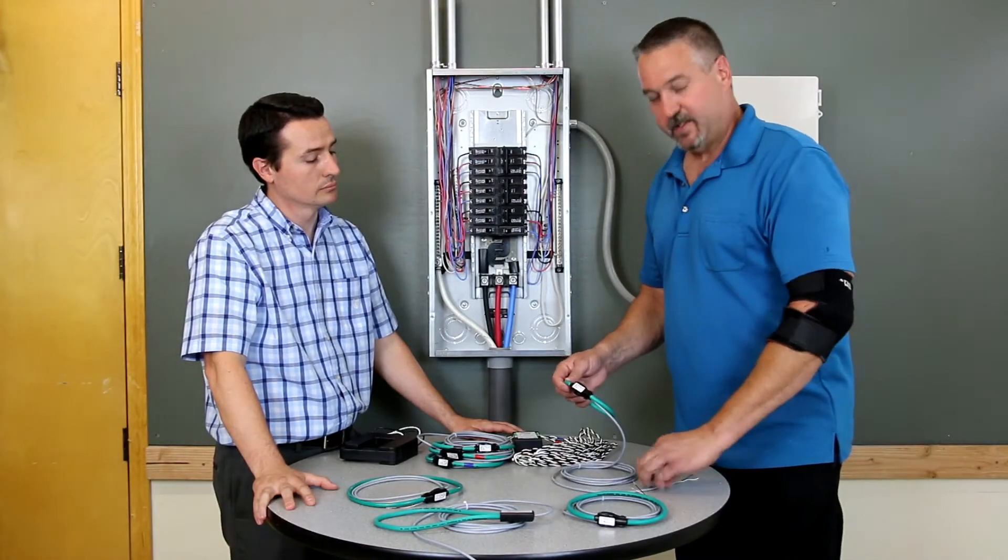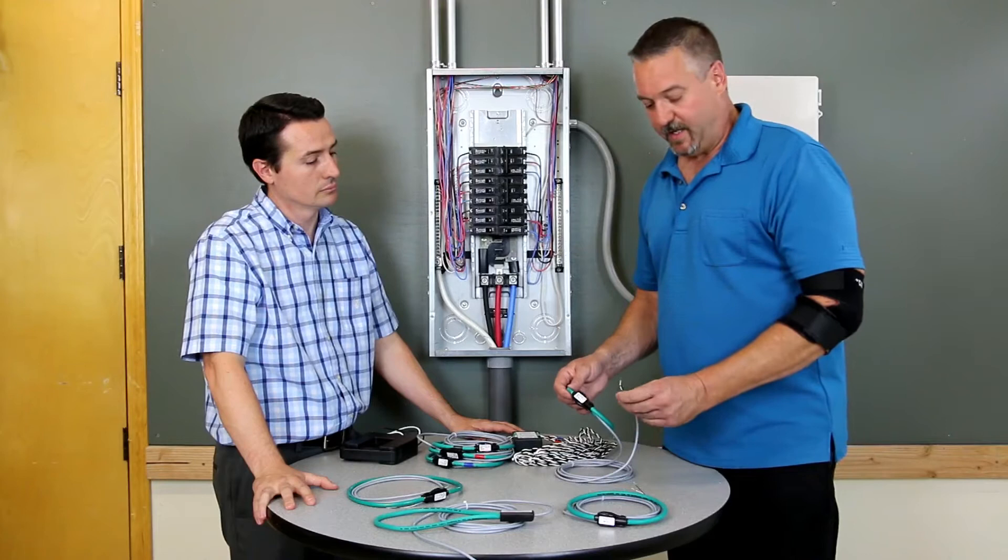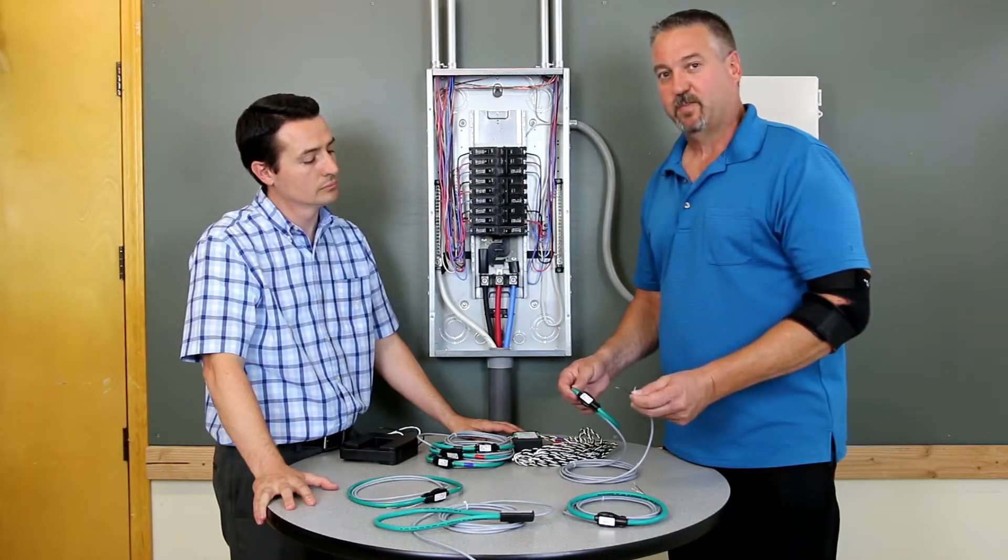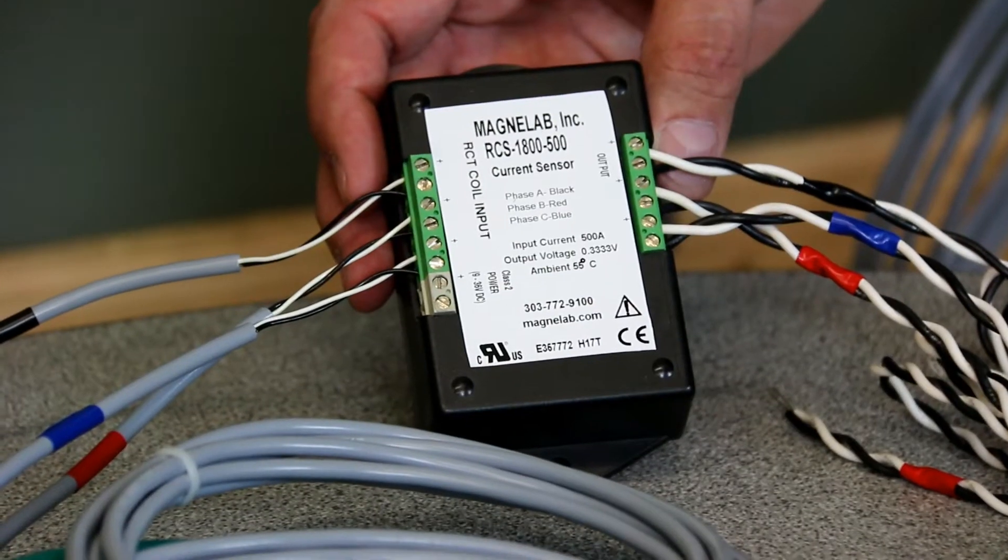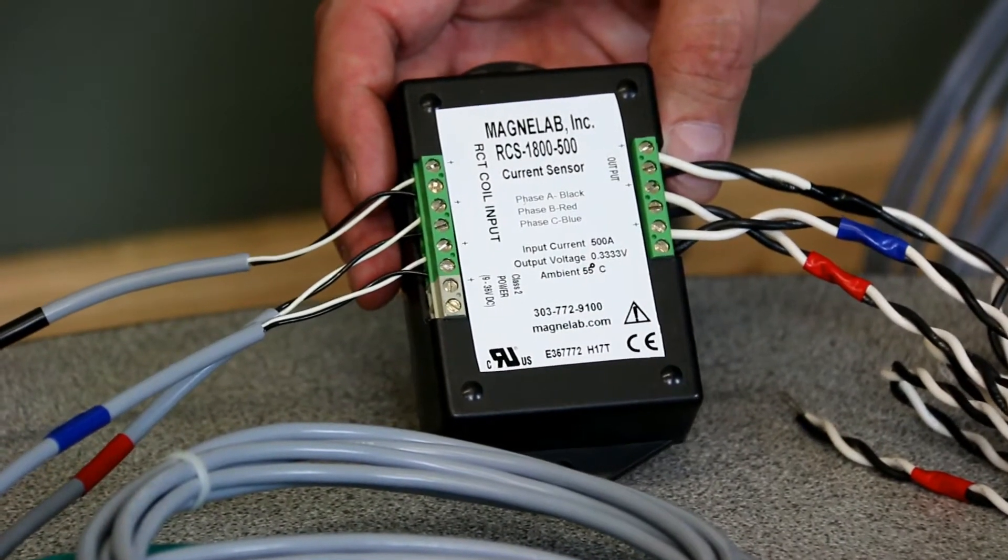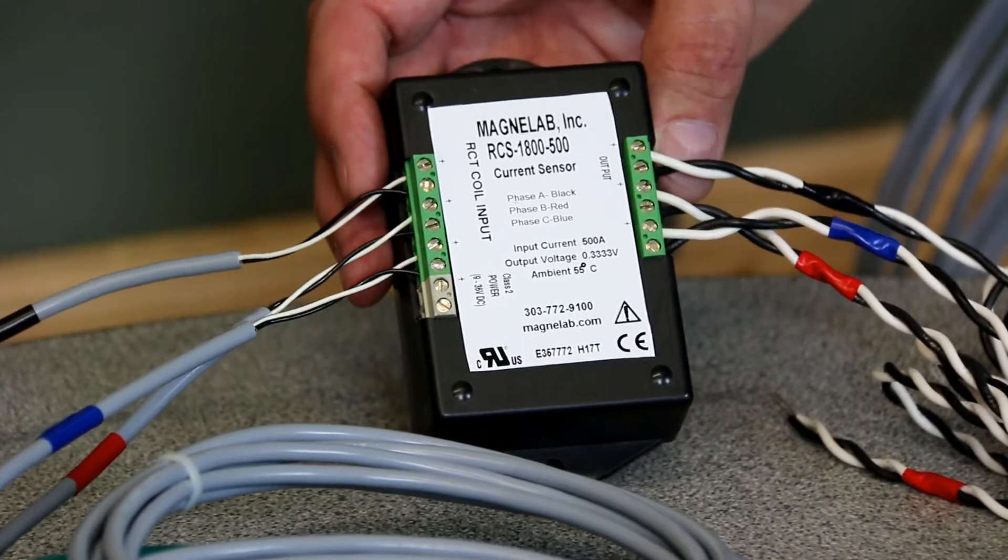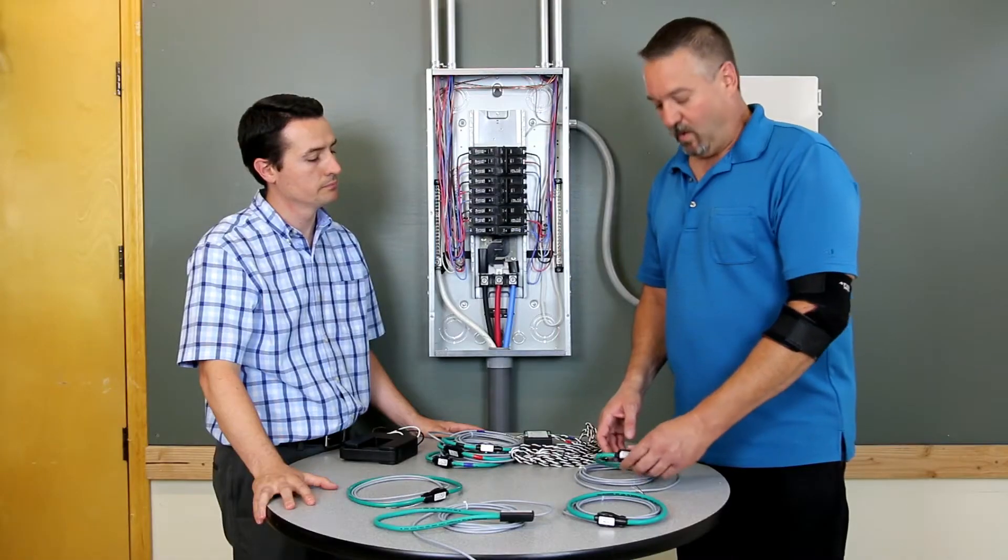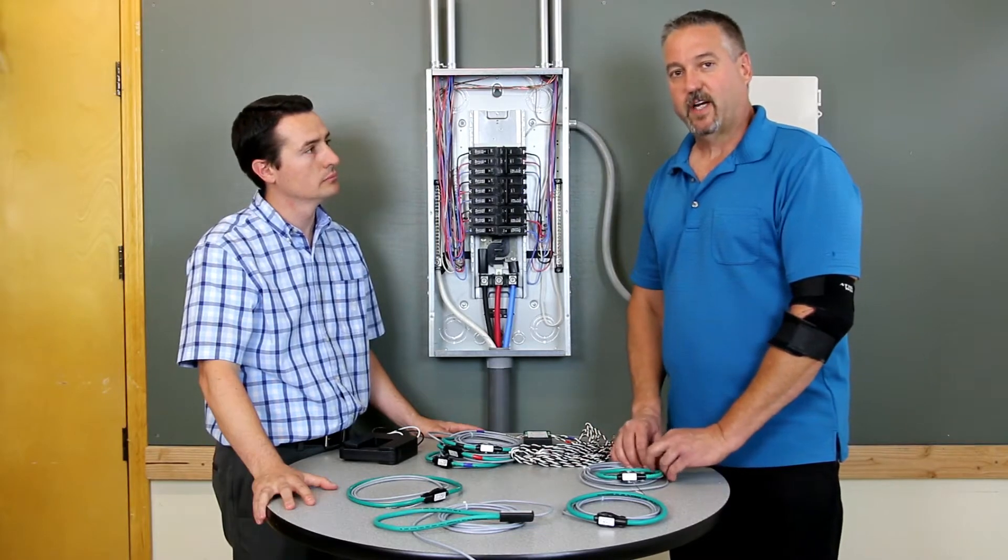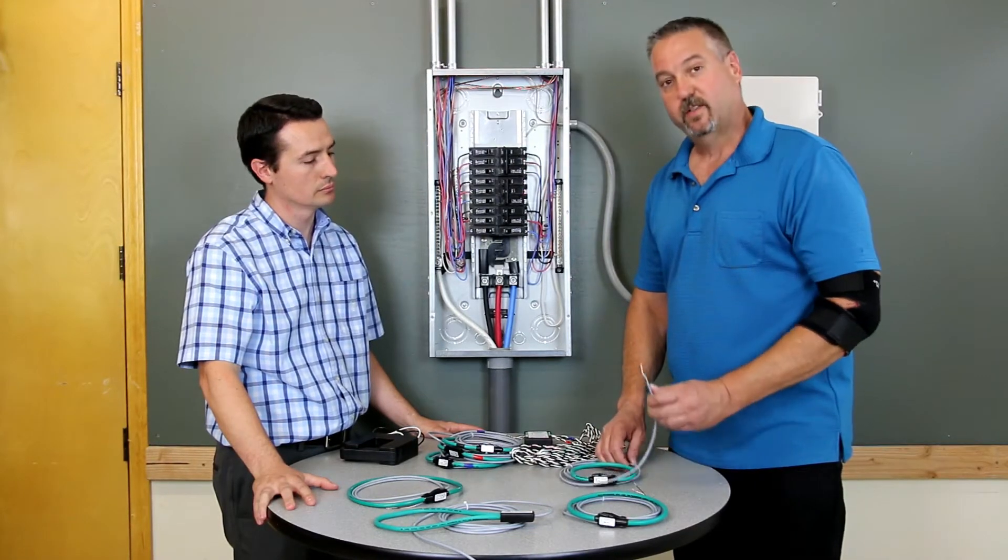The output is a voltage output that in our case runs 70 millivolts per thousand amps through the center of the coil. That then is put through a Magnelab integrator which converts that to a third of a volt, which is a standard in the industry at your rated current. In some cases there are meters out there that can take the raw output of the coil directly.